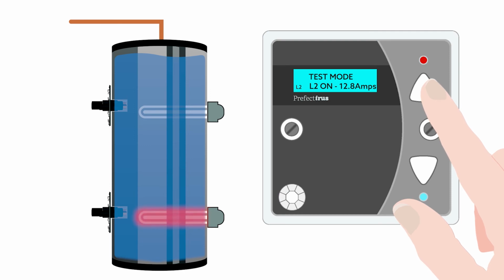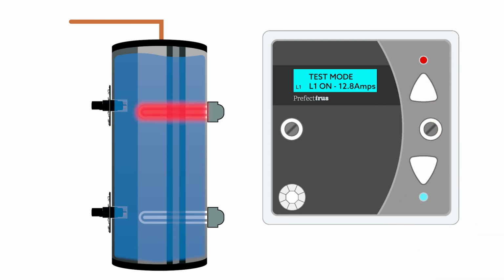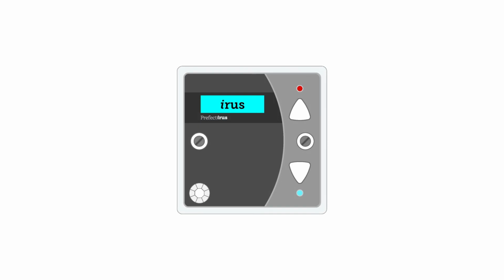To test the upper element, press the up button twice. L1 will now display, and the top element will switch on. Likewise, amps being drawn will be displayed on the screen. It is important that the control unit is commissioned as soon as possible after installation. This will ensure minimal disruption to the users of the tank's hot water.